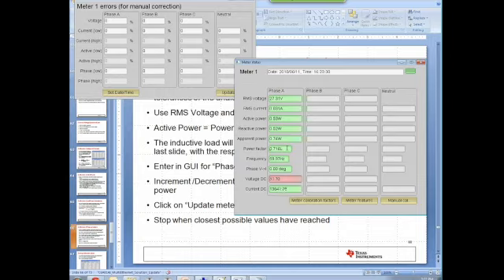As long as your power factor gets approximately close to 0.72, and your active and reactive power are almost the same but not quite, you're going to get about as close as we can get here in the lab or in this building. In the laboratory, using a reference meter or reference generator, we can accurately inject whatever phase shift we want, and your customer could do the same. If they're really interested in this kind of data, they'll have the test equipment to put this in and accurately calibrate and measure this result.